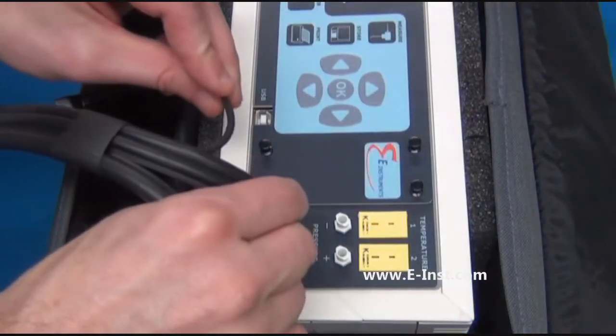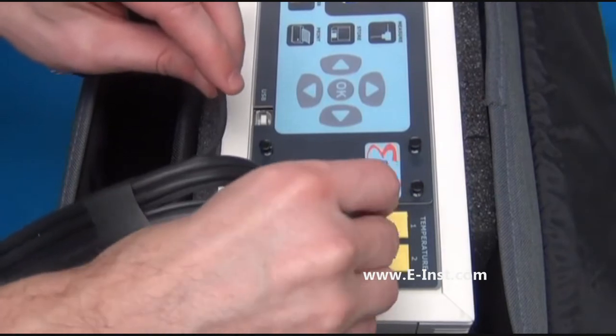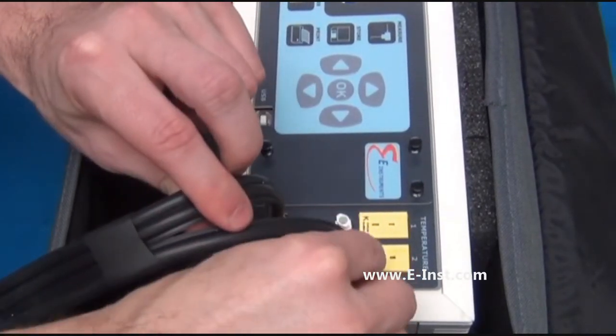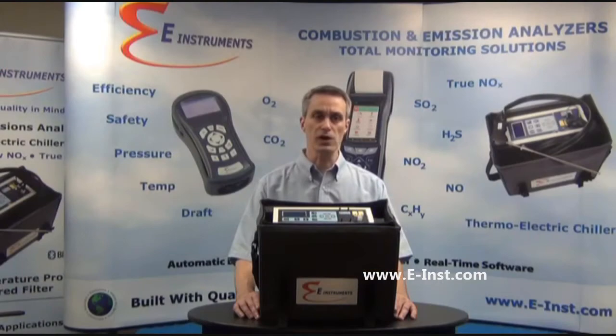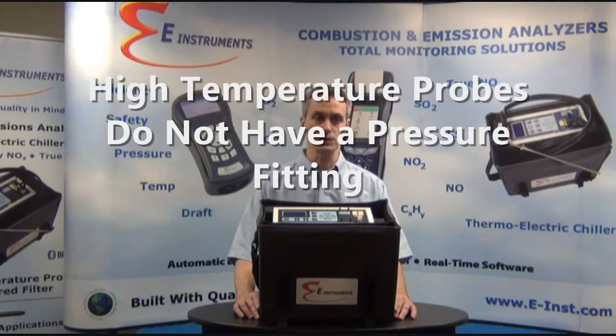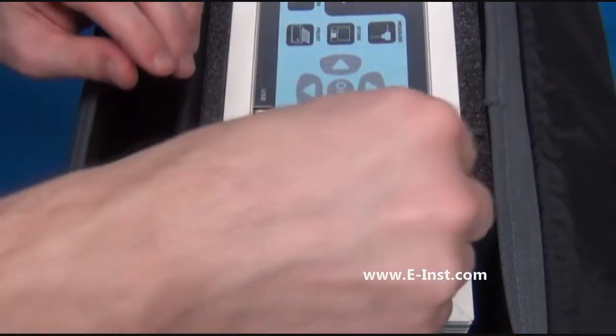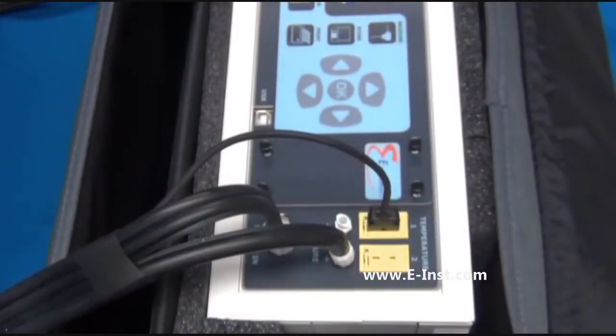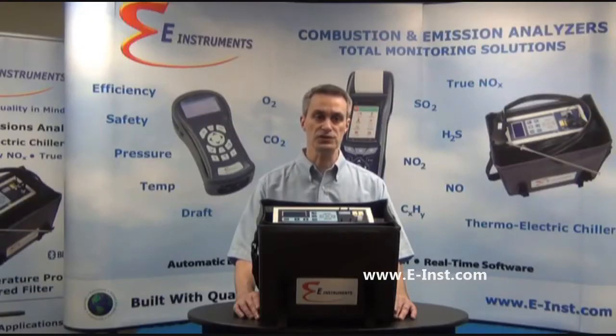One hose pushes into the sample in port on the analyzer, while the other hose connects to the positive pressure port. The long high temperature probes only have a single hose that connects to the sample in port. The probe's thermocouple connector pushes into the yellow temperature number 1 input. Now you can insert the probe into the stack and start your combustion analysis and emissions monitoring.